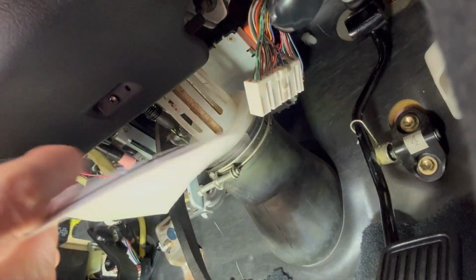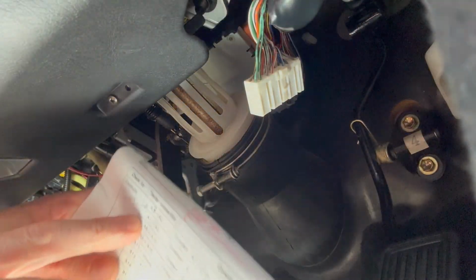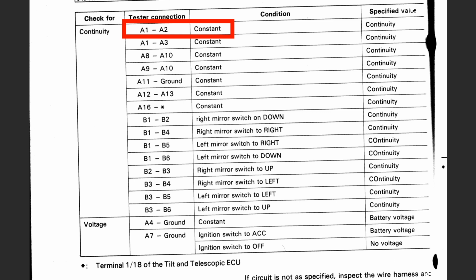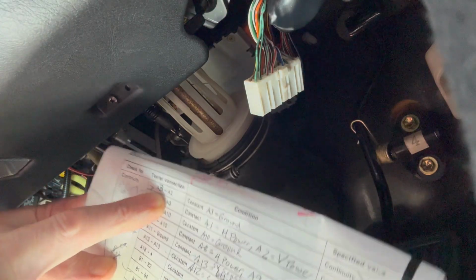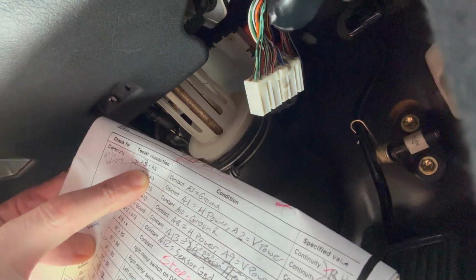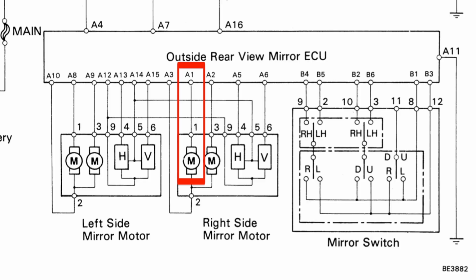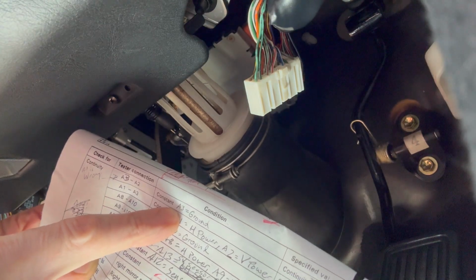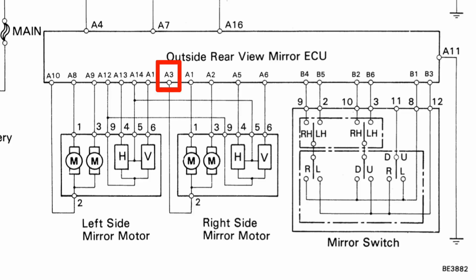This first test that's listed is wrong. It says A1 to A2 originally, but that should be A3 to A2. The reason is that A1 is the horizontal power for the horizontal motor, and A2 is power for the vertical motor, so it doesn't really make sense to test continuity between A1 and A2. There's a shared ground for those two, and that's on A3. So it makes more sense to test A3 against both A1 and A2.